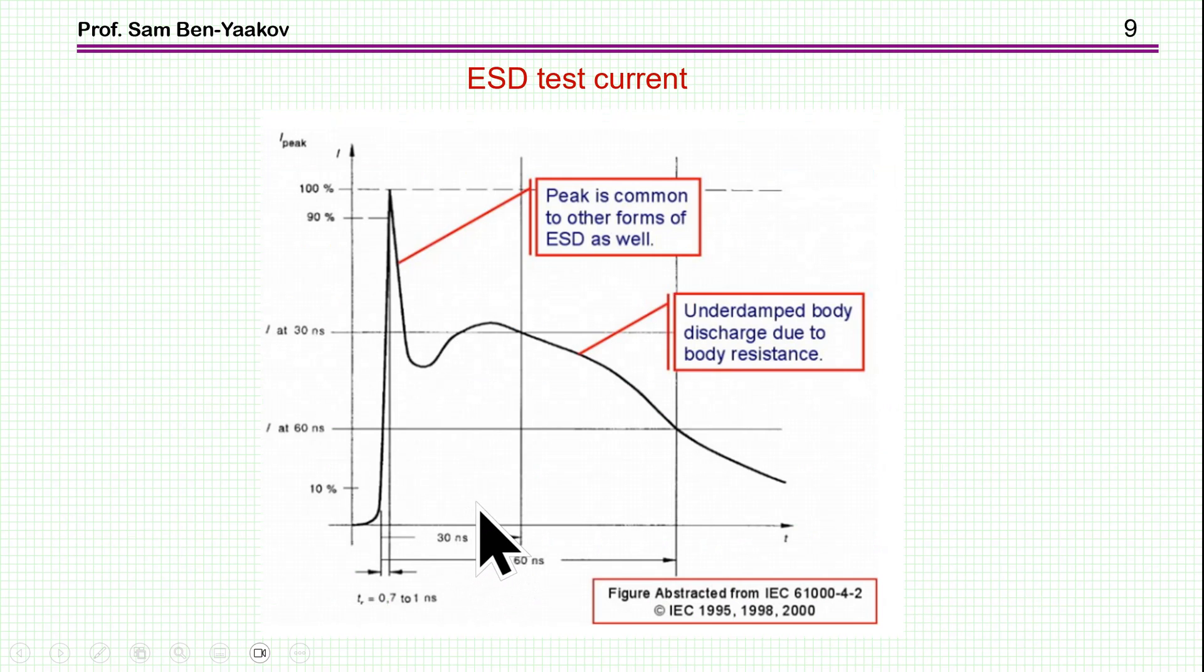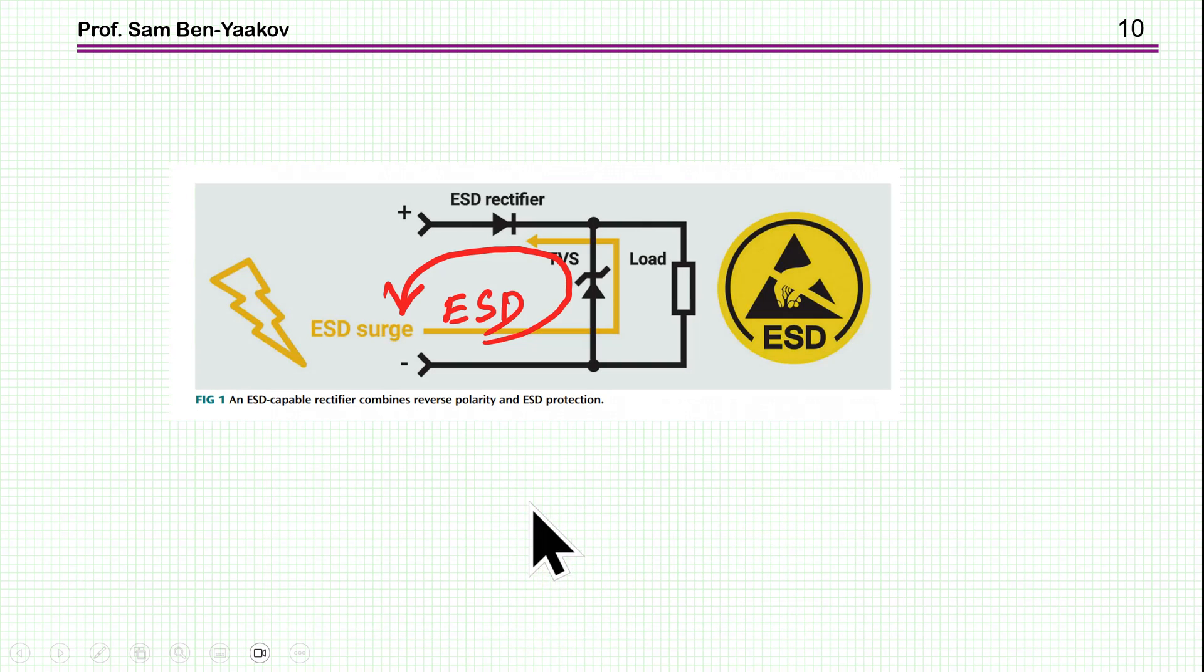And here is the waveform from the standard. This is the formal waveform. And here we are talking about the current. So the current is going up to 100% at a very short time. It's a very fast rise time. And there is some sort of an oscillation. And the total here, up to this point, is 60 nanoseconds. And as I've said, we're talking about a 100 nanosecond pulse altogether from start to just about end.